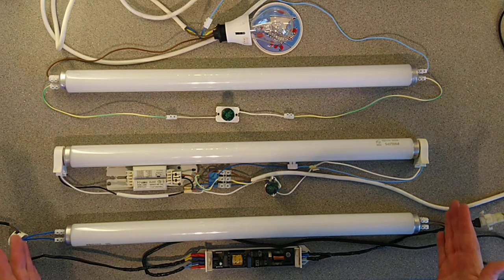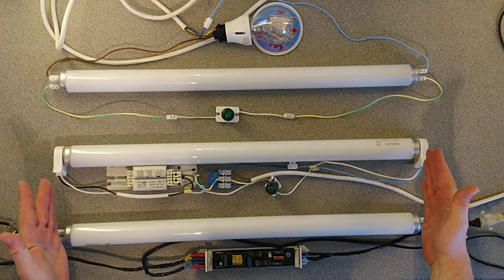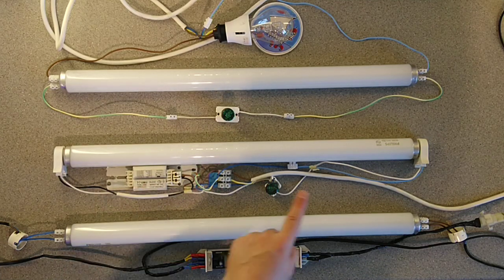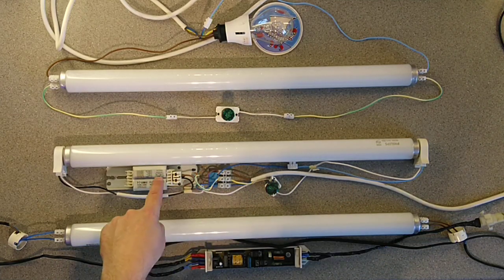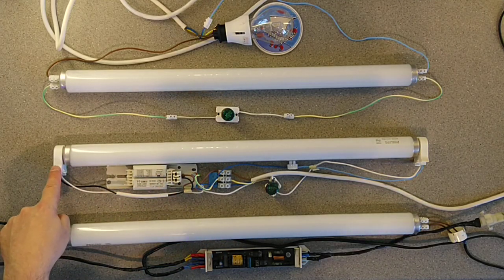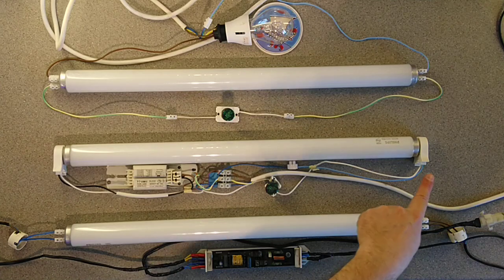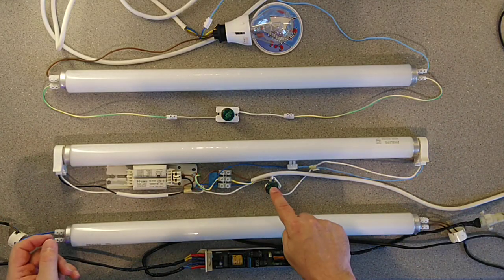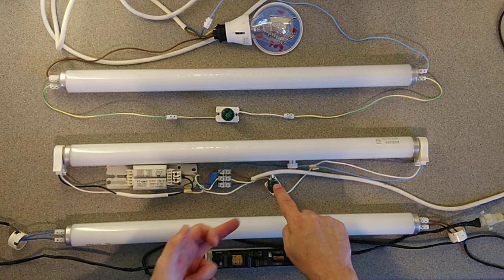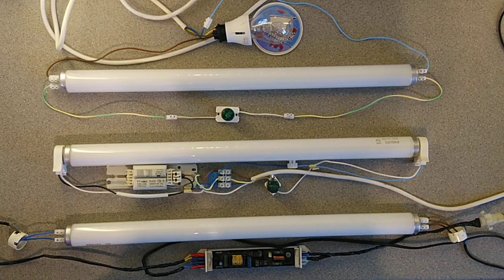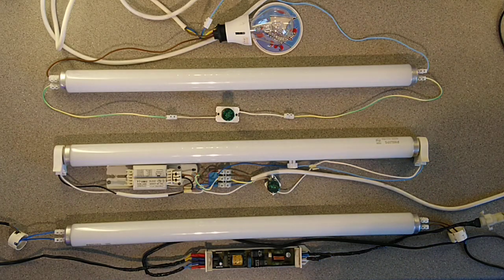Number two is a magnetic ballasted lamp. The live comes in, goes through the magnetic ballast and goes to one end of the tube. The neutral comes to the other end of the tube, and the starter, which is an electronic starter, is going to control the lamp. The reason I've used electronic starters is so that the lamps all have a chance to come on together.